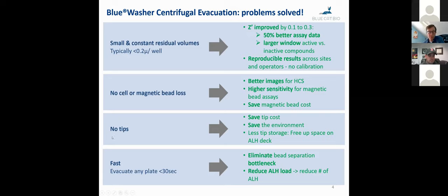You have no tips, which of course limits the cost of them. It also saves the environment. And when you look at how to organize your liquid handler, it frees up a lot of space on deck because you don't have to store all those tips. And finally, it's really fast. The blue washer evacuates any plate in less than 30 seconds, and that's measured from plate drop to plate pick in an automated setting.